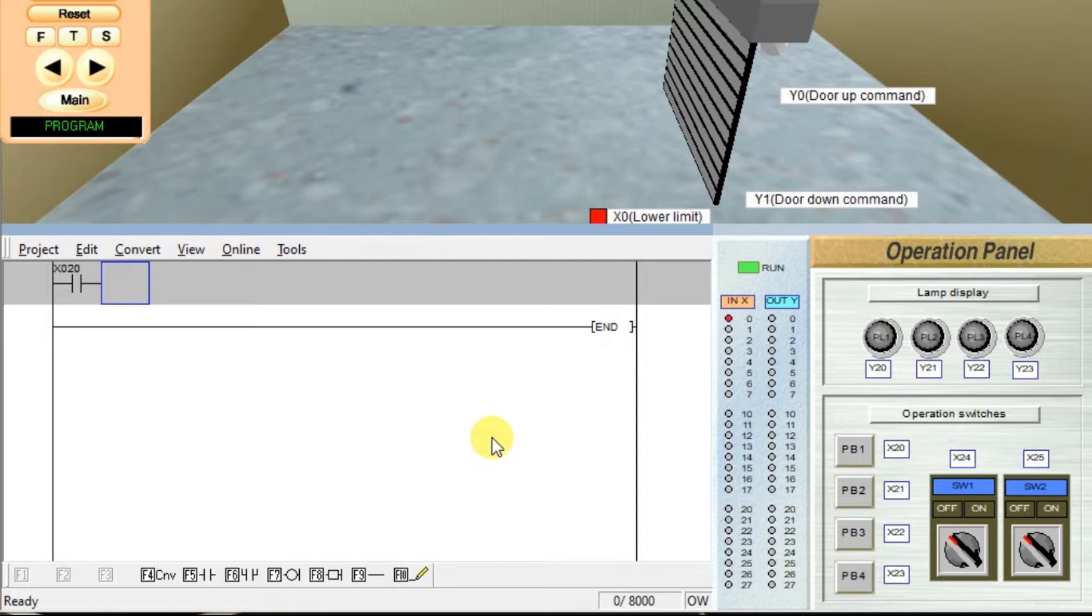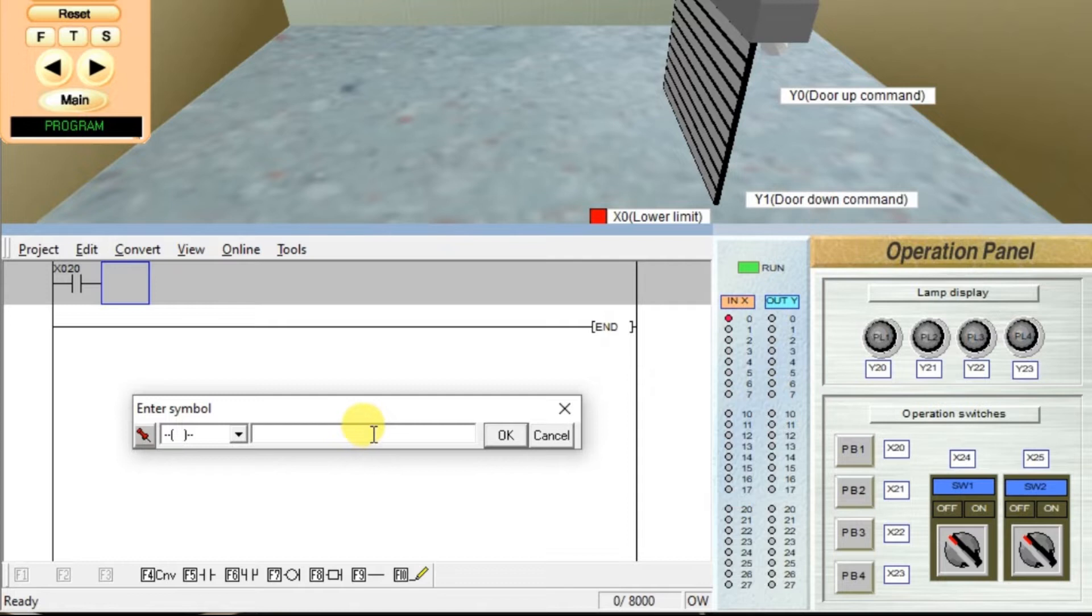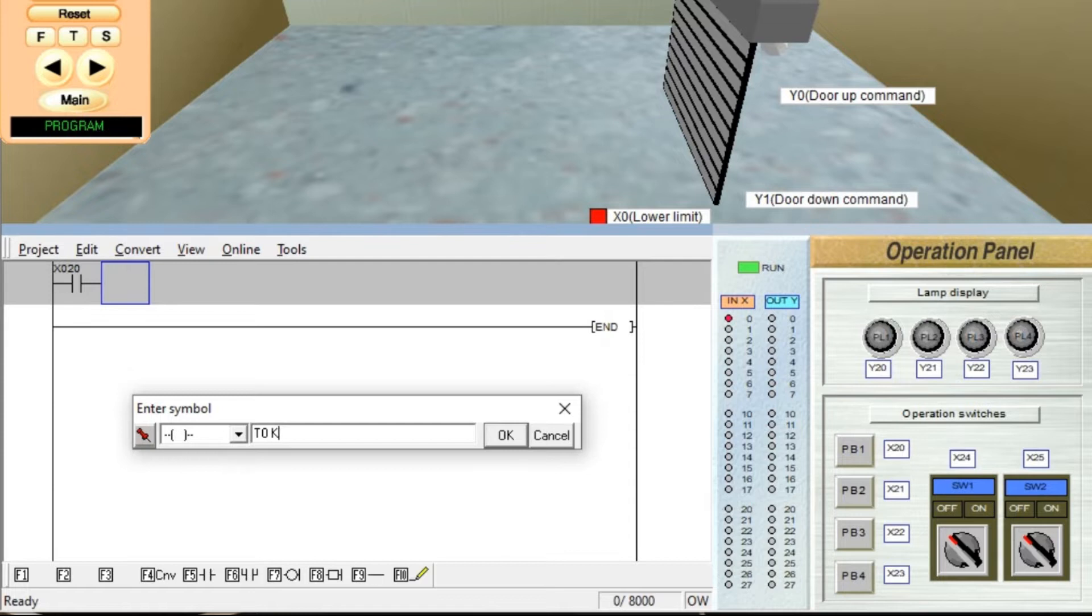And we need one timer. Take output instruction, coil. I am taking T0, space, constant K and then your required delay. How much delay is required? 5 seconds. So enter 50, click OK.